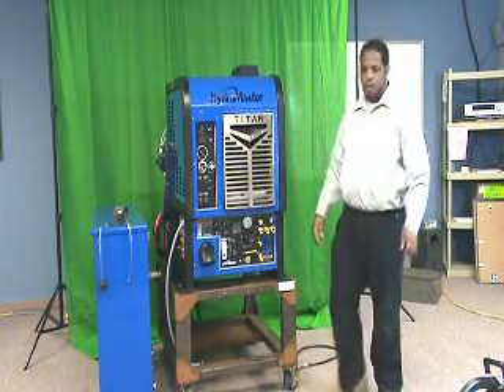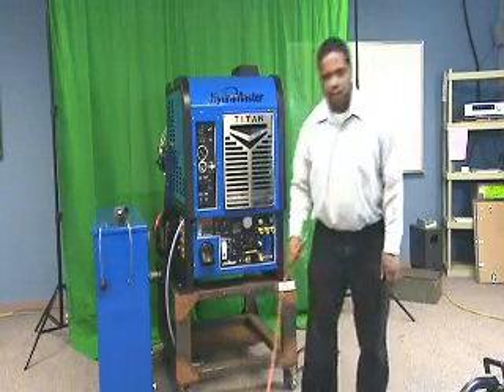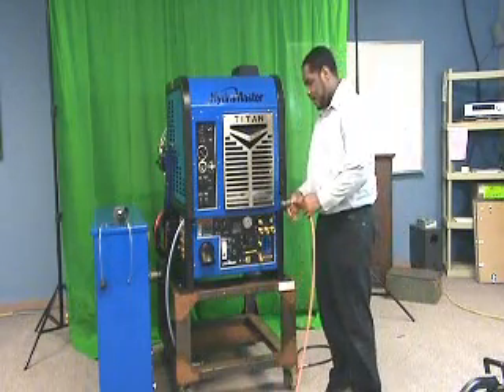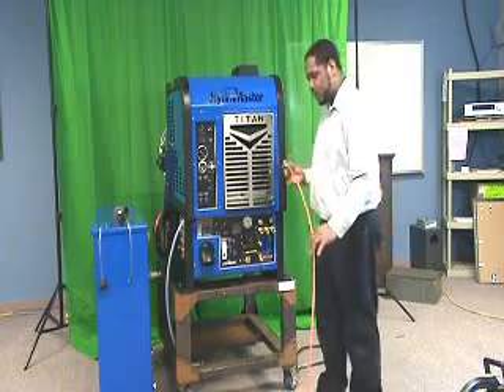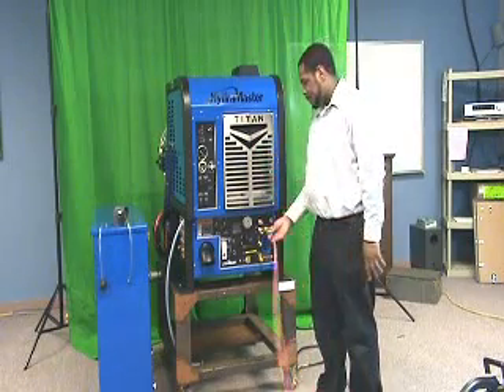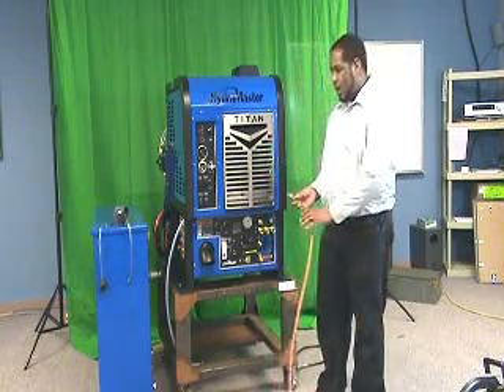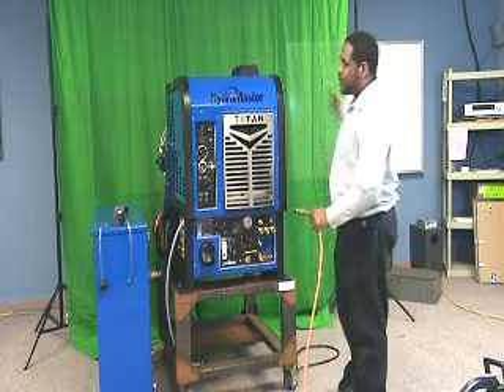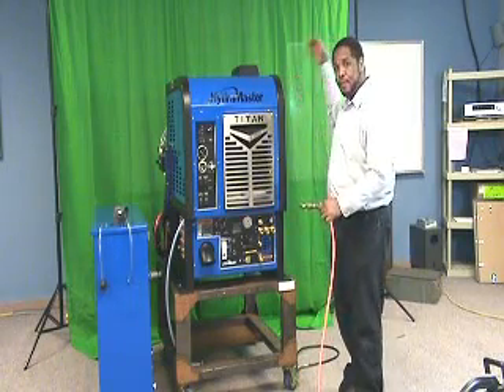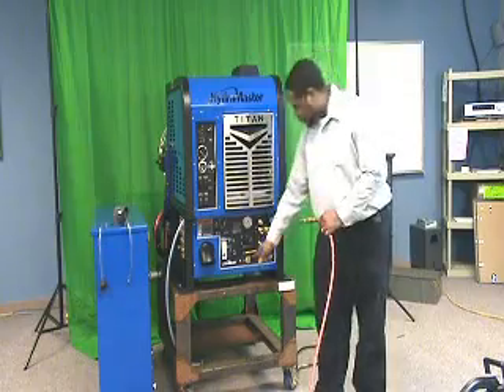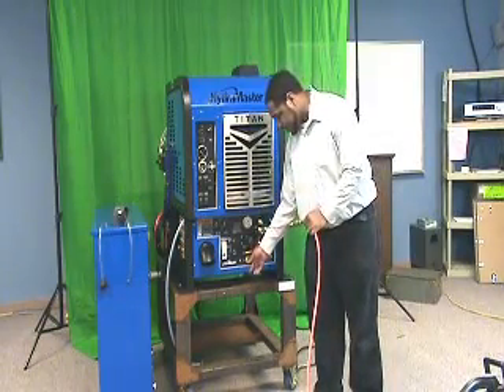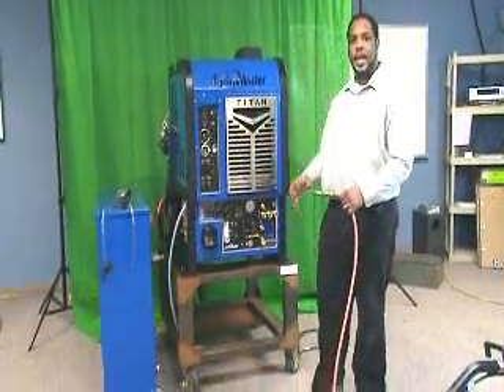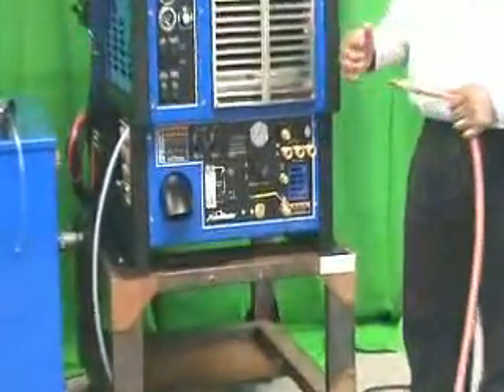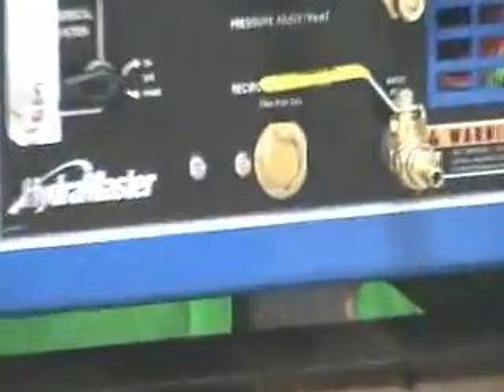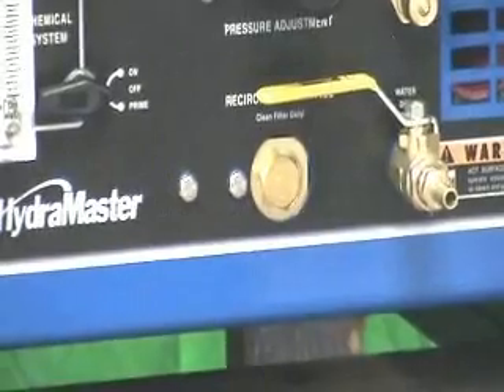We recommend, instead of using your tool, that you acquire a male fitting with just a regular hose attached to it with the other end being open. This allows you to drain all the fluid out. So you're going to fill your water box with water to try and flush the system. We have a screen/filter in place that will catch most of the heavy deposits, but for the smaller deposits, to get that out, that's where you would connect this open-ended hose to your solution outlet.